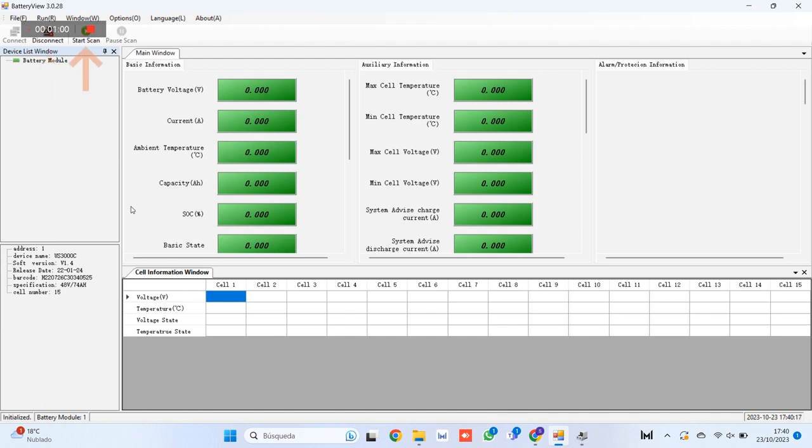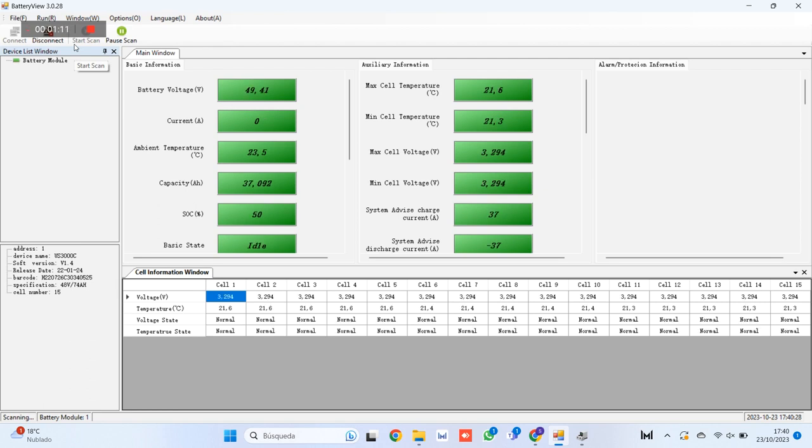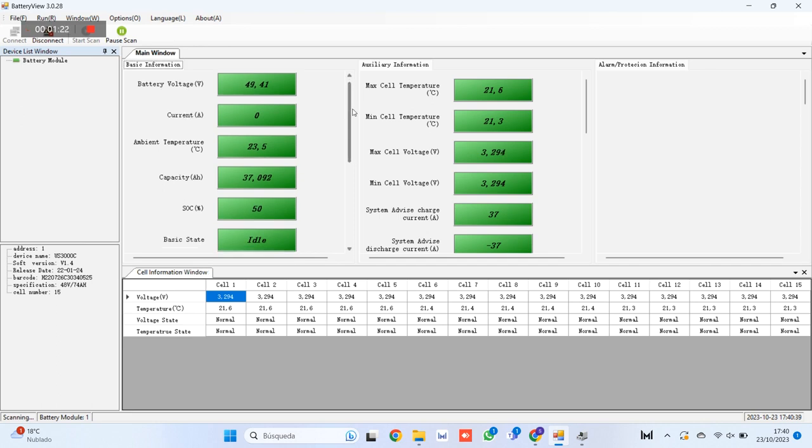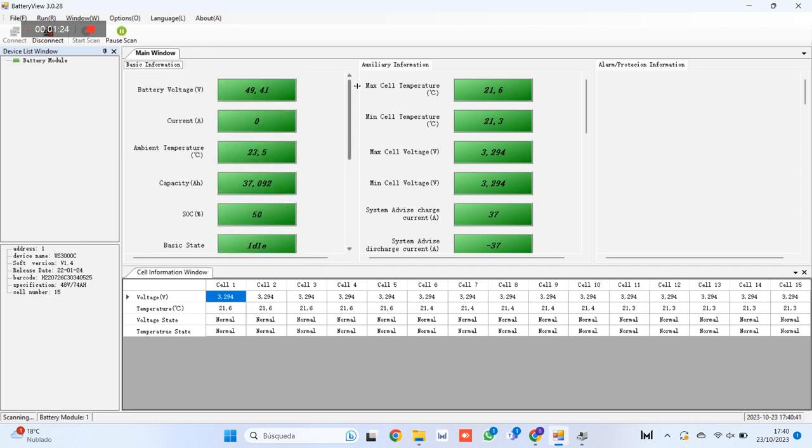Step number 6. Click on Start Scan to be able to see the parameters in real time of our battery. You can see how in the lower left part data such as the communication address of the battery, software version, number of cells, serial number and other data start to be displayed. Once started, data is displayed in the main window and cell information window tabs.